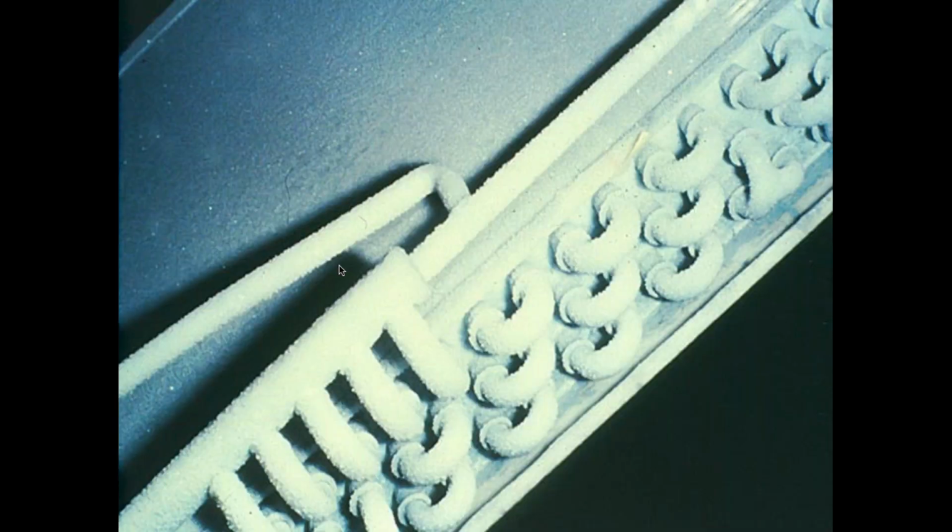Coil defrosting. The coils sometimes are iced so much. I have seen the drain pans totally full of ice. Even if you defrost the coil, the water which is falling in the drain pan spills over and falls into the cold room, because in the drain pan, an ice slab is formed, a total ice slab. So such things should not happen.